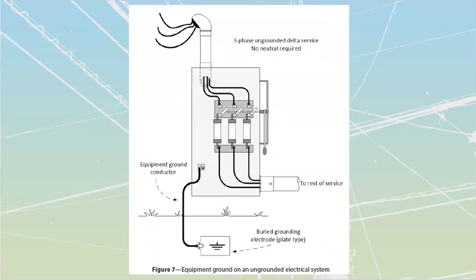Equipment grounds are going to happen inside of third year. You have not covered these, but we do have some systems that don't have a neutral. They're going to be three-phase systems referred to as delta. At that point, we do still have to have a ground on the system just to surround everything and provide a fault path back, but it's not going to be tied to a neutral. We just refer to that as an equipment ground.